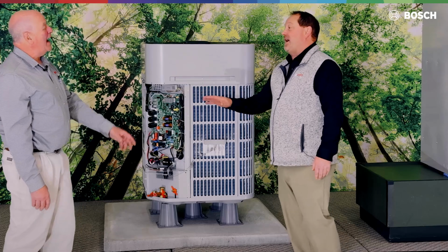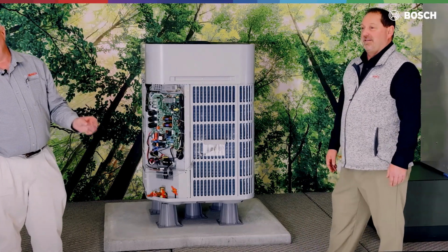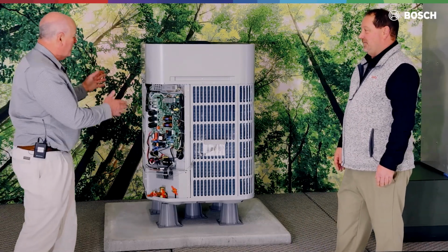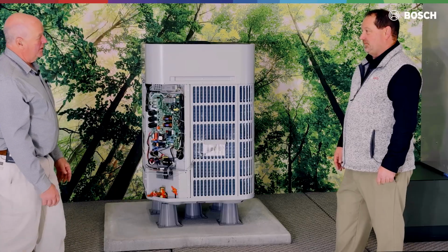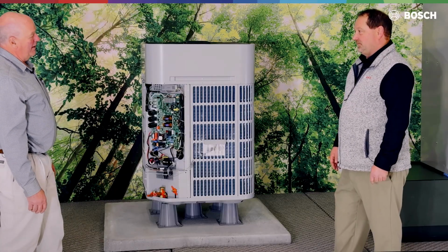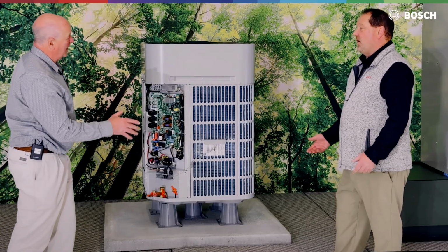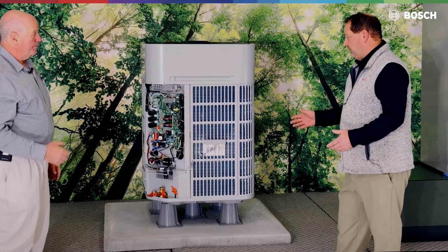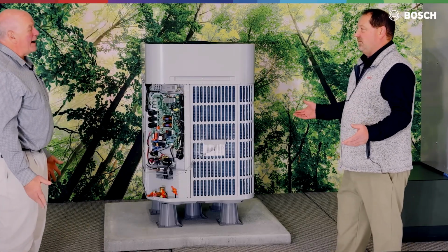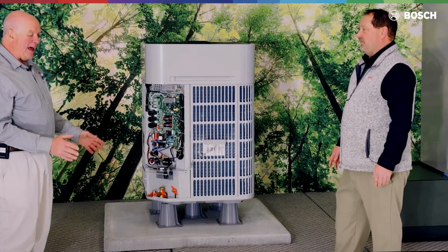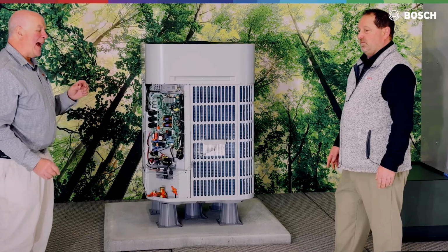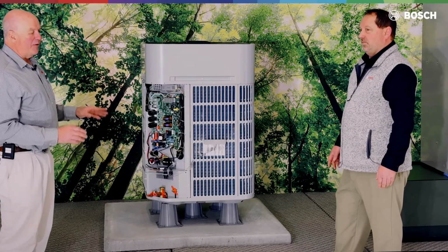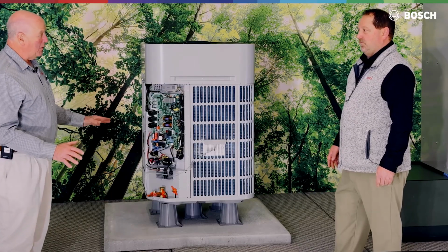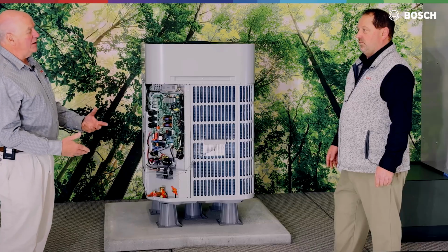You are much better at math than I am. 81 ounces is the maximum you should ever add on a 5-ton unit that we're working with. All right? That's with the 150-foot line set, again. Okay. That's probably going to put us somewhere around a 15-pound total system? Perhaps. Okay. So that is critical, guys. Too many people don't add that charge at the end. If we're 15 foot or less, we don't do anything with the charge. If we're over 15, we need to add.